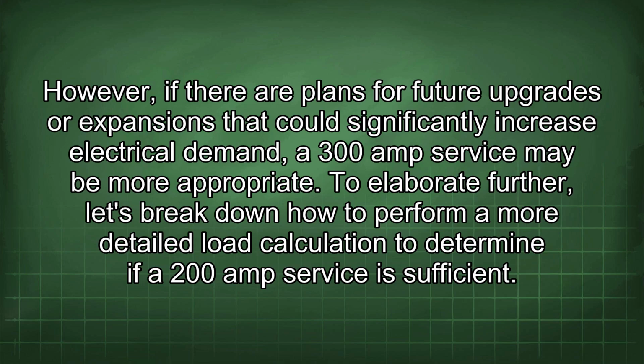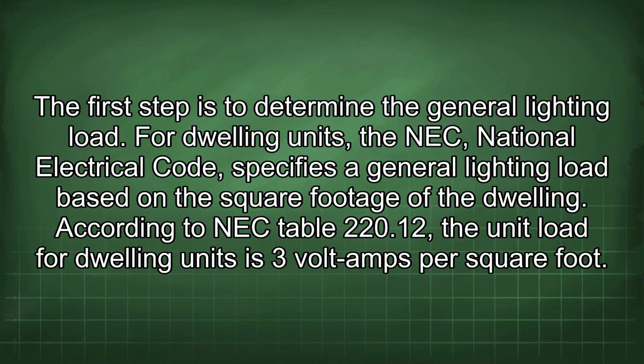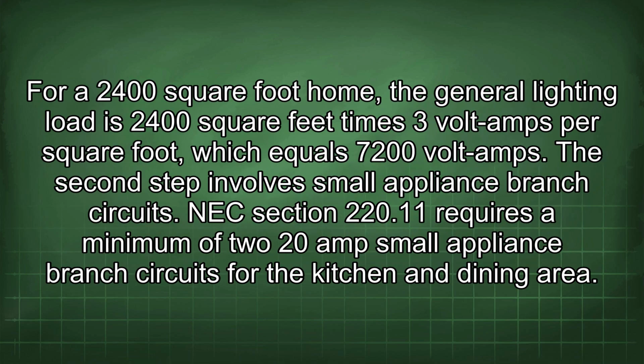However, if there are plans for future upgrades or expansions that could significantly increase electrical demand, a 300 amp service may be more appropriate. To elaborate further, let's break down how to perform a more detailed load calculation to determine if a 200 amp service is sufficient. The first step is to determine the general lighting load. For dwelling units, the NEC, National Electrical Code, specifies a general lighting load based on the square footage of the dwelling. According to NEC Table 220.12, the unit load for dwelling units is 3 volt amps per square foot. For a 2400 square foot home, the general lighting load is 2400 square feet times 3 volt amps per square foot, which equals 7200 volt amps.